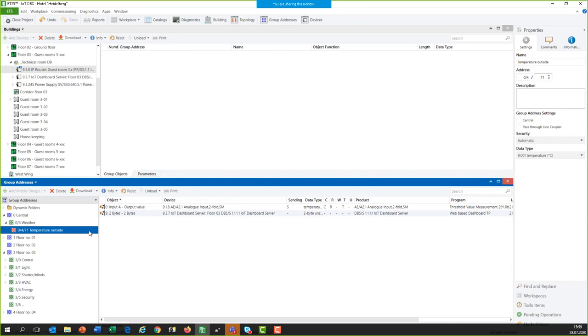When you click on the IP router and go to 'Preview Filter Table', you see group address 0/4/1 is now used across different lines and is now in the filter table. This happens automatically in ETS. For example, group address 0/4/1 is linked to device 9.1.8 (the weather station) and also to the IoT Dashboard Server 9.3.7. That address is then in the IP router of line 9.3 and also in IP router 9.1.